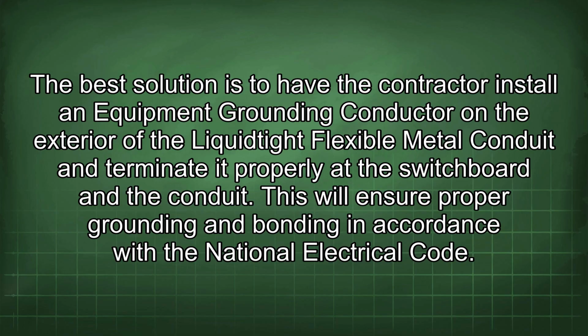The best solution is to have the contractor install an equipment grounding conductor on the exterior of the Liquidtight Flexible Metal Conduit and terminate it properly at the switchboard and the conduit. This will ensure proper grounding and bonding in accordance with the National Electrical Code.